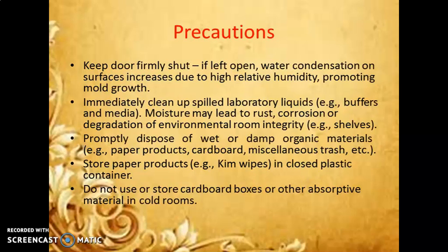Next is the precautions. Keep the door firmly shut. If left open, what happens? The water condensation on the surface increases due to high relative humidity, promoting mold growth. Immediately clean up spilled laboratory liquids, for example, buffers and media. Moisture may lead to rust, corrosion, or the degradation of environmental room integrity, for example, shelves. Promptly dispose of wet or damp organic materials, for example, paper products, cardboard, miscellaneous trash, etc.